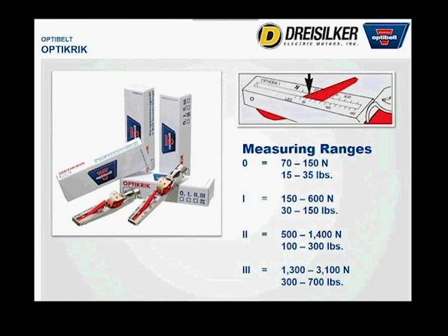This is very simple. You put your finger in it where you see the little loop, then press down on the middle of the belt, it clicks, and you read it off the gauge. When that little lever comes up, that's the tension you have in the belt. Then you move the drive in or out to tighten or loosen it based on that number versus your recommended number.